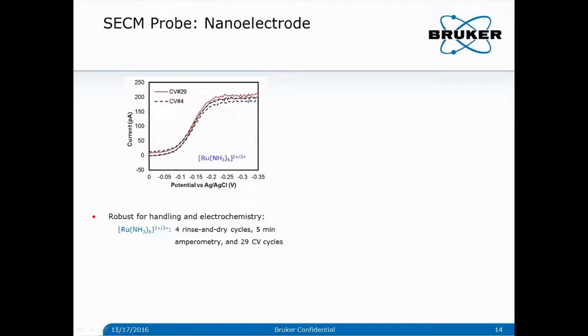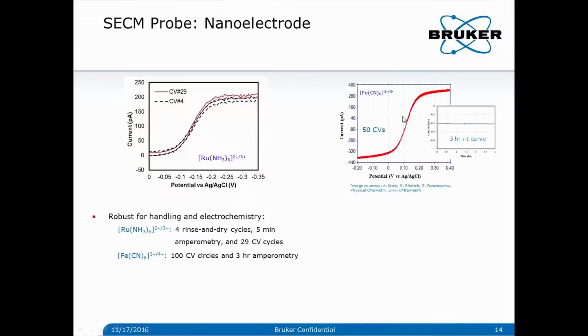We're showing 2 CV curves here. These 2 CV curves were recorded before and after a sequential handling and EC test. This handling and EC test includes, for example, 4 rinse and dry cycles, 5 minutes of amperometry, and 29 CV cycles. From the comparison here, no degradation of EC performance is observed. And here's another example, the EC performance test in a ferrocyanide solution. As you can see, these are 50 continuous CV cycles plotted together, and you will see no difference at all among these CV cycles.